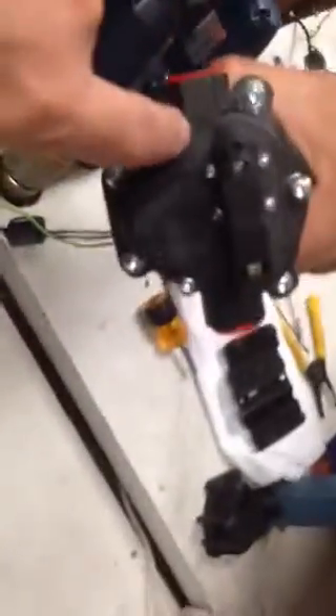Normally it pumps left to right. You see some directional flow arrows here. So this is the right position, left to right. The pump head is there. The bolt holes are at the bottom. That's the same pattern as it was before. Now these same three fasteners are going to be tightened down to 26 foot-pounds.